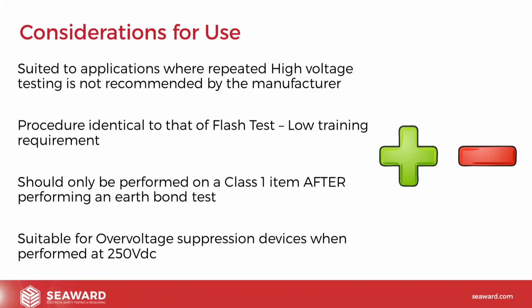Considerations on a class 1 item: you should only perform this test once you've performed an earth bond test. It's important that we know the earth bond is connected and the earth cable is doing its job before performing any class 1 leakage test, whether that's a flash test, an insulation resistance, or the protective earth conductor current test that we speak about a little bit later. Now, why is it important? Well, if the earth cable wasn't there and we hadn't performed an earth test on it, we would never have a return path for the leakage current. So make sure you do your earth bond test prior to doing any level of insulation resistance or any test on the insulation at all, because the test is relying on the earth cable to be there in order to get a good measurement.